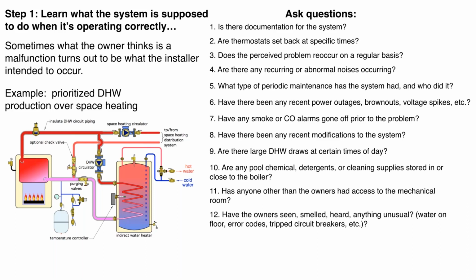Does the problem occur on a regular basis? For example, if we go back to this indirect water heater in the priority zone, let's say in the morning there's 3 or 4 showers taking place, and consistently we notice that bedroom number 3 is a little bit cool when that happens. That's probably a hint that, let's go back and see what's happening in the system on a repeated, consistent basis. That is perhaps the underlying cause there. Ask them, are there any recurring or abnormal noises in the system? Hydronic systems that are operating correctly should be relatively quiet.